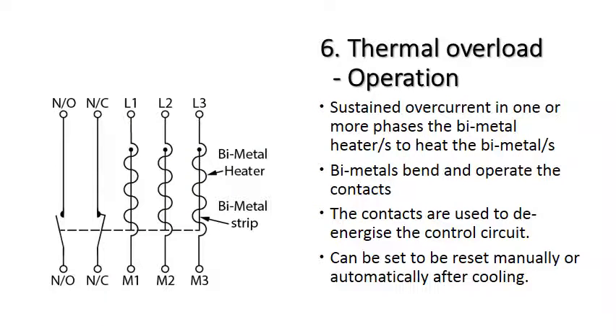So with the thermal overload, like we said in the last slide, sustained overcurrent or a short circuit in one or more of the phases heats the bimetals, and the bimetals bend. Eventually they bend far enough to operate the contacts of the control circuitry. Once again, they can usually be reset manually or automatically after cooling. The thing with thermal overloads is, because it's heat that's bending the bimetal, it takes a while for the bimetal to cool down again and be ready to be reset. So there is a bit of a time delay there, which can cause an issue.